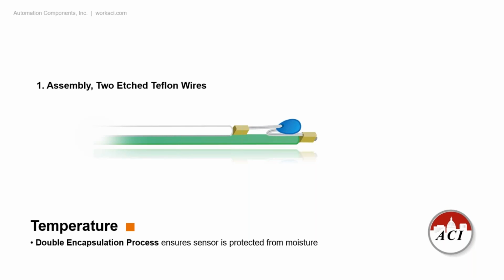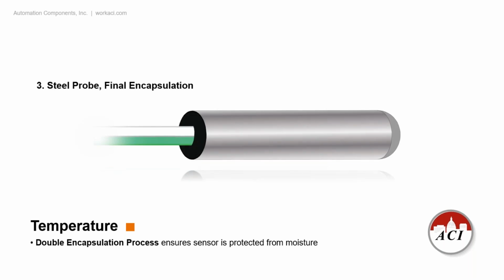So there's no thermal transfer or heat transfer at all in the process of concealing that thermistor lead to the lead wire. So we crimp it the first day, and then that night, we encapsulate that into a plastic tube. And we let that seal overnight. So it's like a viscosity of Elmer's school glue, and then it hardens overnight. And then the next day, we take that plastic tube that's encapsulated with thermal transfer compound, and we encapsulate it again into a stainless steel sheath and completely fill that sheath up.